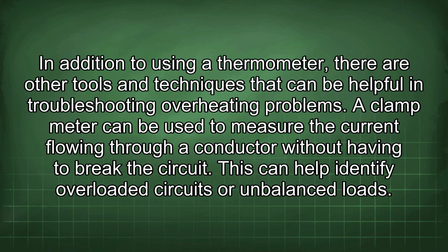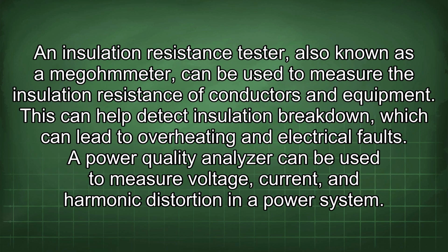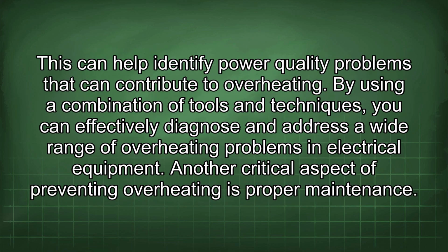This can help identify overloaded circuits or unbalanced loads. An insulation resistance tester, also known as a megohmmeter, can be used to measure the insulation resistance of conductors and equipment. This can help detect insulation breakdown, which can lead to overheating and electrical faults. A power quality analyzer can be used to measure voltage, current, and harmonic distortion in a power system. This can help identify power quality problems that can contribute to overheating.